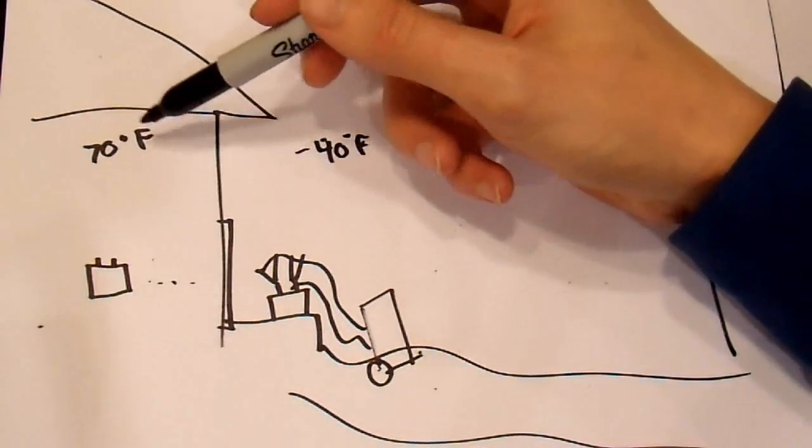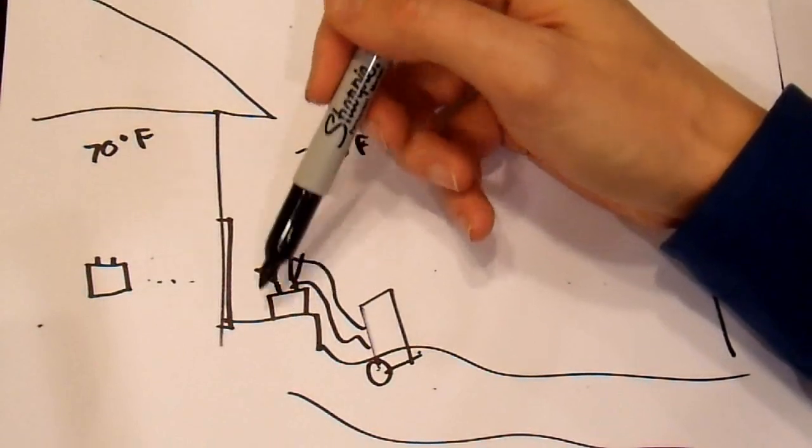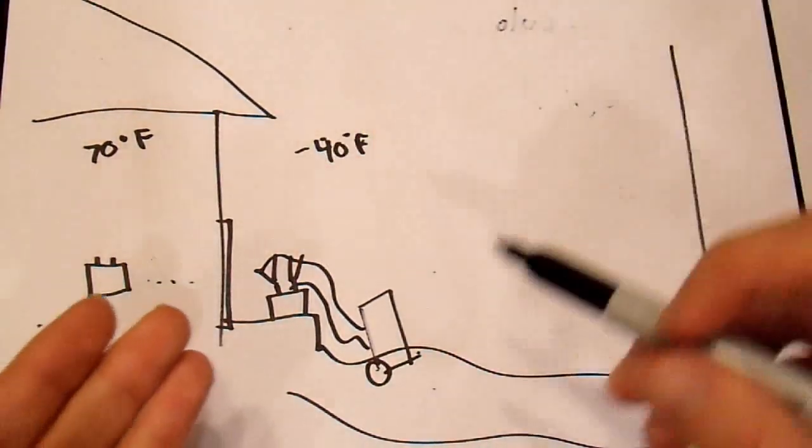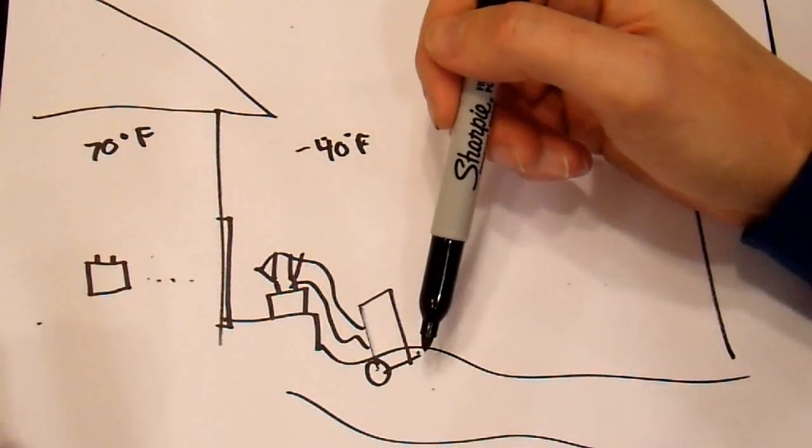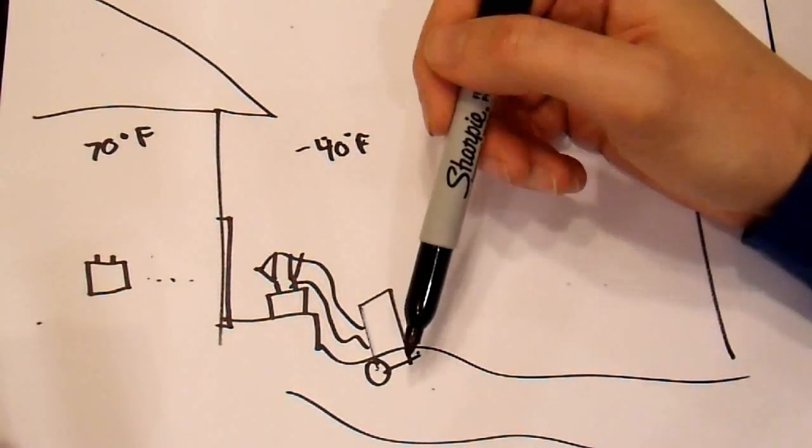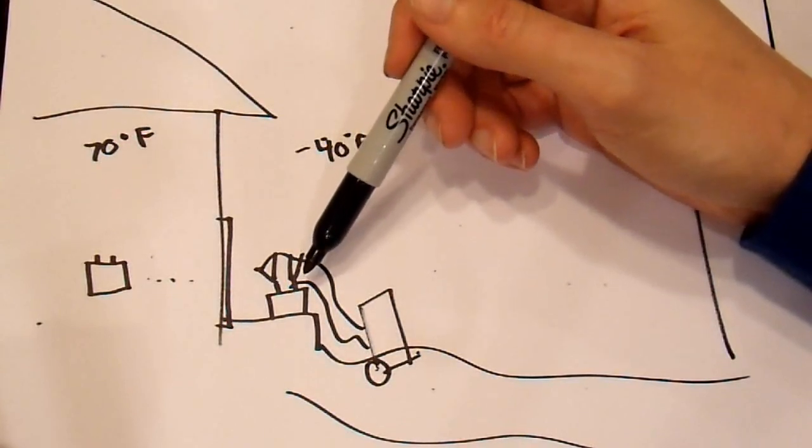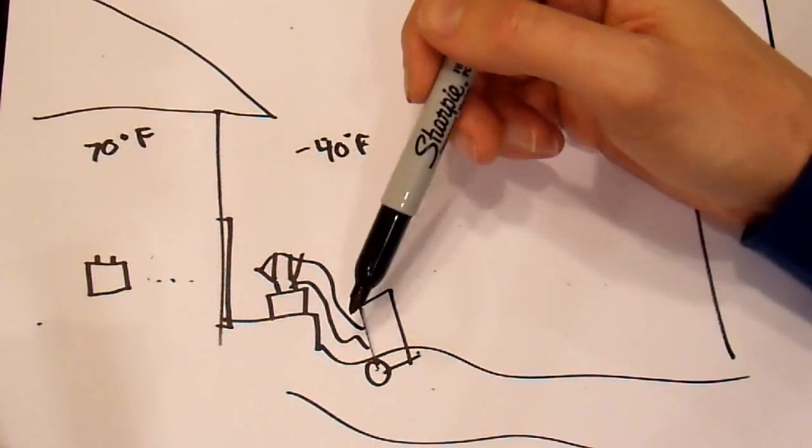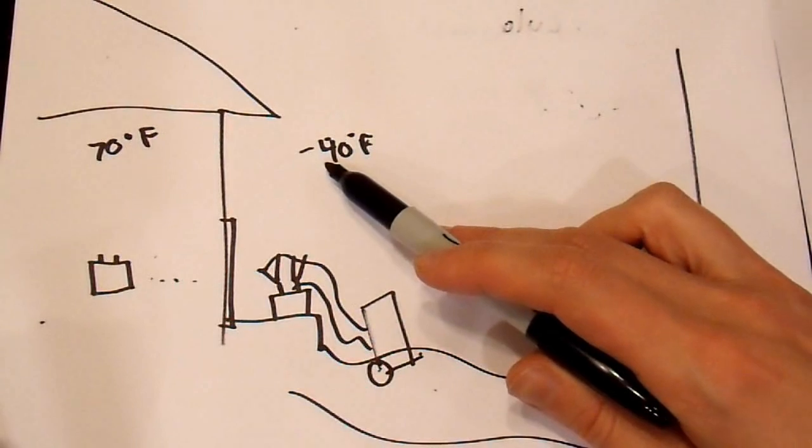Because if I discharge this battery, it took 100 amp hours out of it and then set it outside and let the battery cool off. Well for one it would freeze solid, but we'll ignore that. And I put it on this charger, I would have to put in more than 100 amp hours to bring this back up to capacity. But how's that possible? It's at minus 40 and this graph clearly says that it's about 15 percent available capacity.